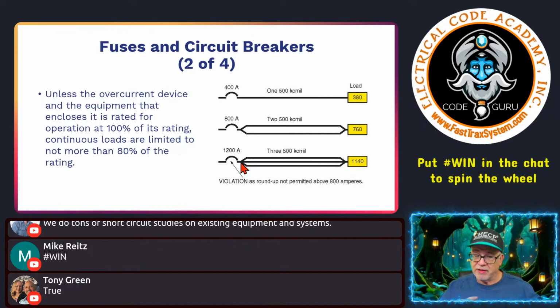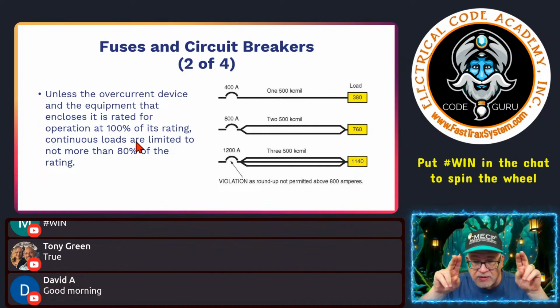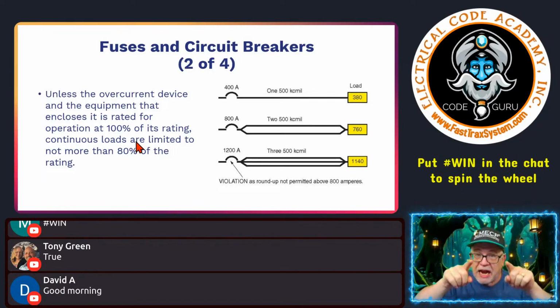Important that you know the difference. That's what's so important about the NEC, being able to realize what all you've got going on. You've got services, with very limited protection on those service conductors. Only overload protection is available, not short circuit ground fault protection. And then, of course, once you get past the service, you get everything downstream, feeders and circuit breakers for branch circuits. Then we have to start worrying about all these additional rules, because we're only as good as that overcurrent protected device. So manufacturers of those devices, make sure you're doing your job right, because we're relying on you. Don't want to be getting recalls all the time for overcurrent protected devices.